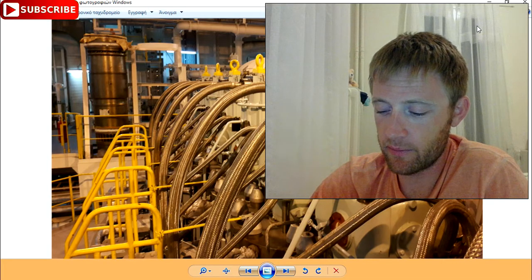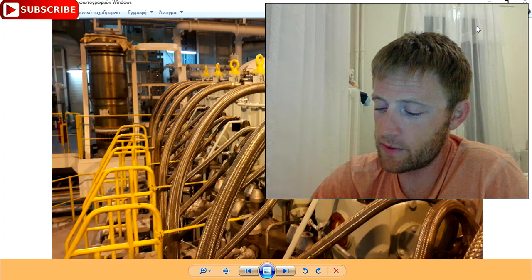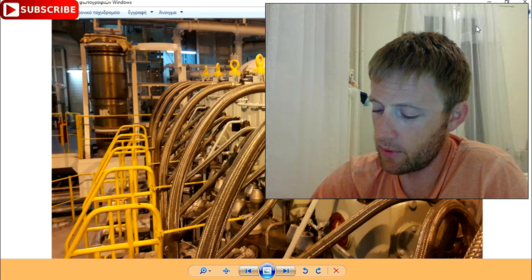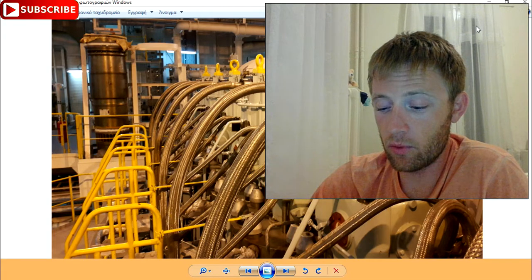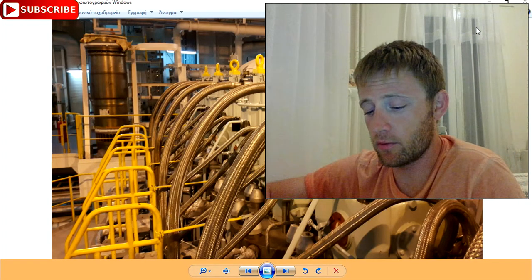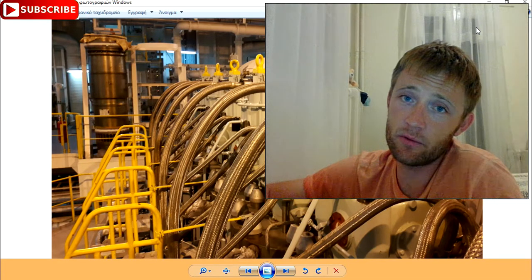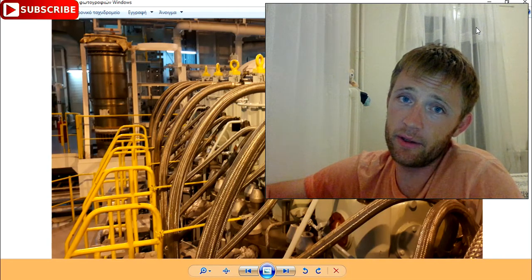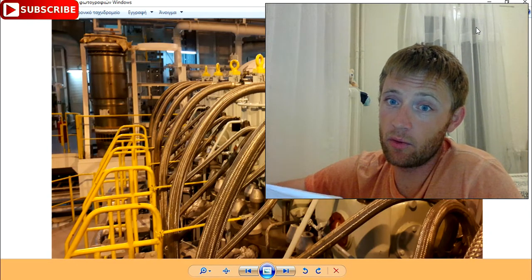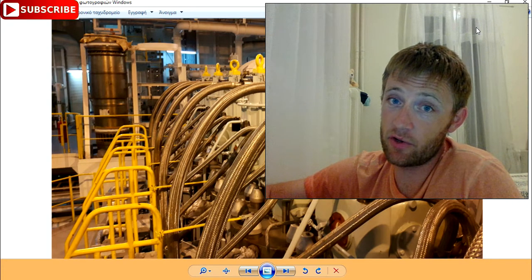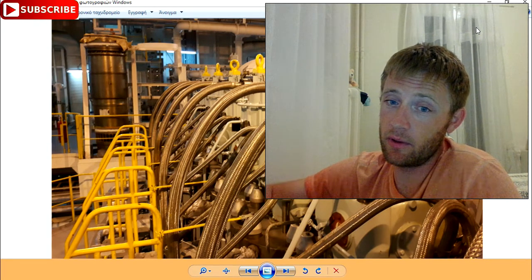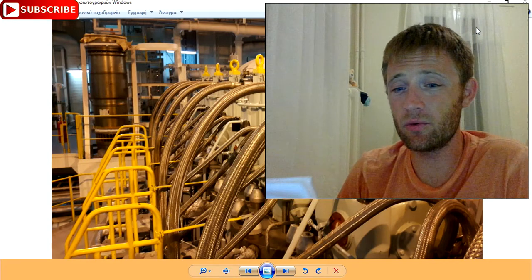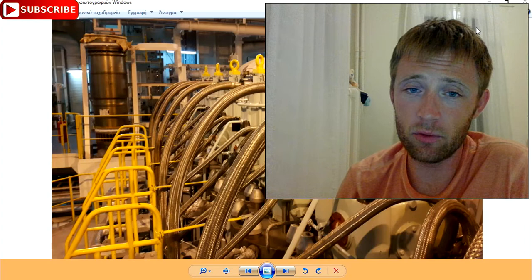Okay. Number seven. The system has a sensor which is set at 50 degrees, and it opens the circulation for cooling to the oil cooler, okay? And at 30 degrees it closes again. At 50 degrees it opens and sends oil to the cooler for cooling. Sure, the oil will heat up. As time passes and the oil is circulated through the system, high pressure is obtained. High pressure means excess heat, okay? And high flows also produce heat, so the oil will increase in temperature, so we need to cool down our oil.